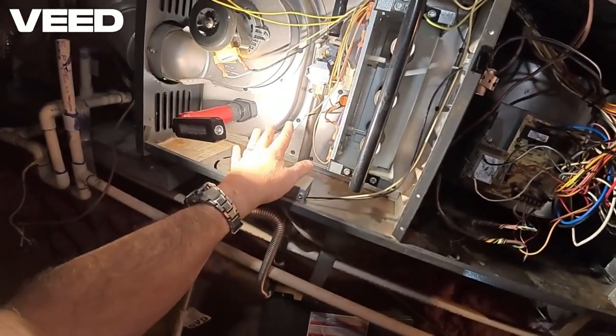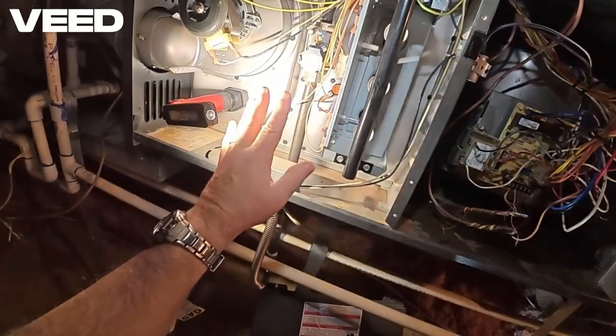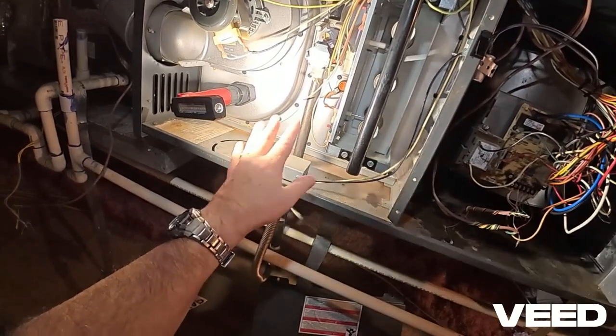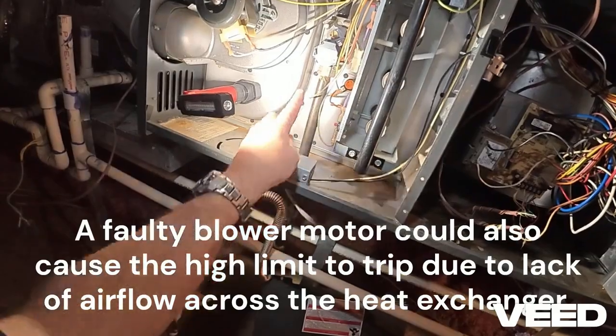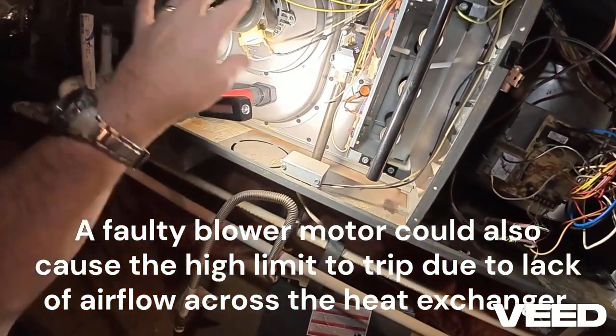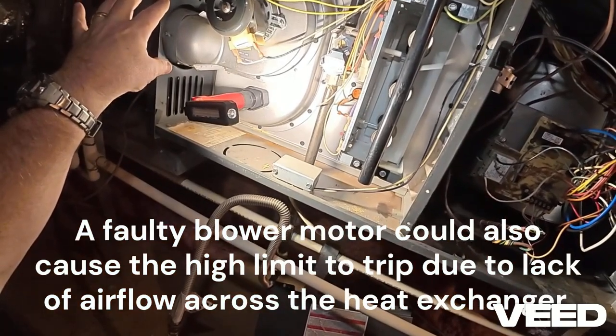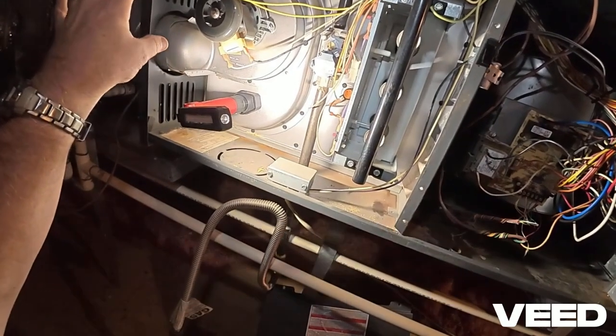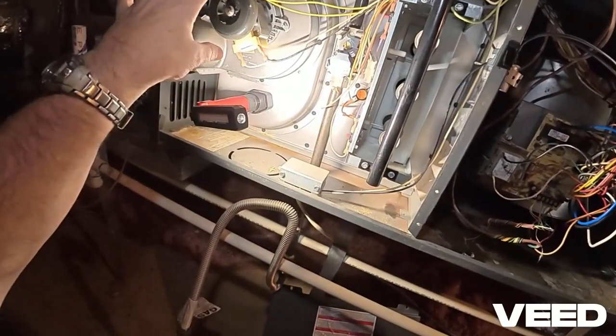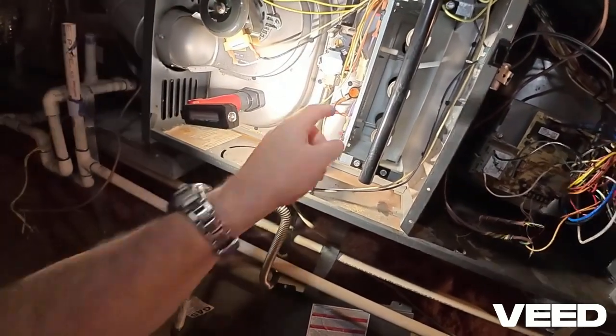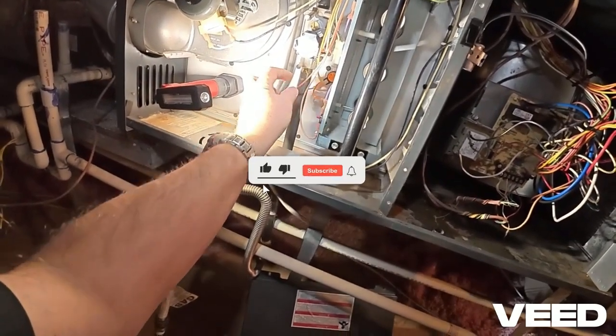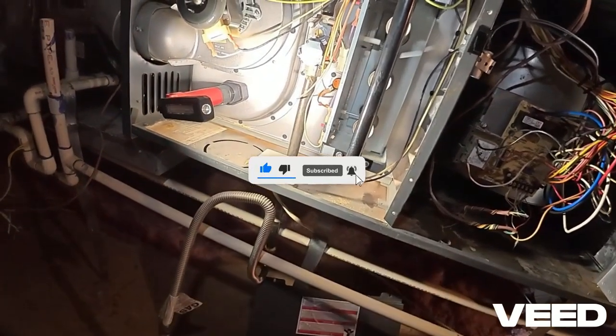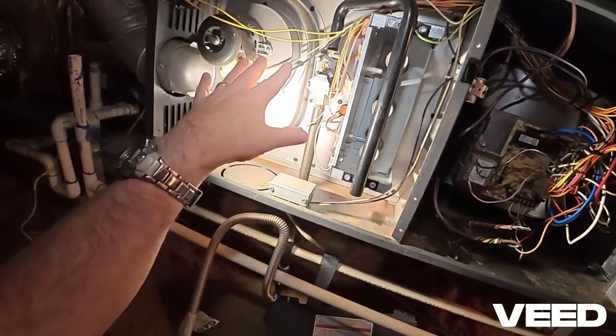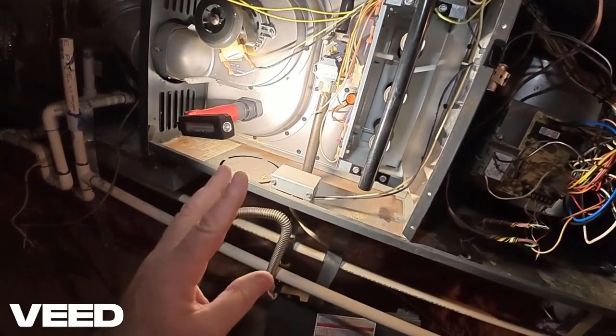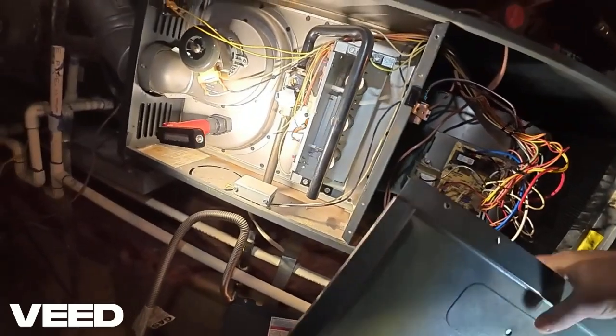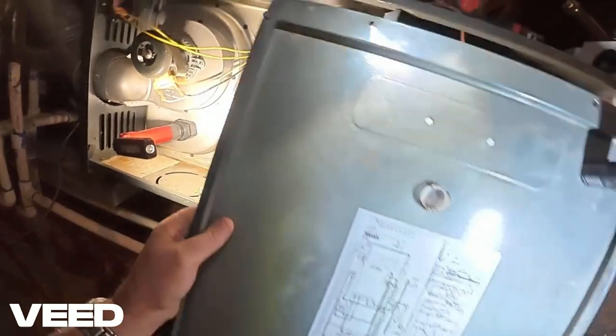So this is a safety. If you have a problem, say with a dirty filter or closed registers, and you have an airflow issue and it's not getting enough air across the heat exchanger to pick up and remove the heat, it will overheat, and this will open up and send a signal back to the control board of a fault and turn off the system. So that's the role of the open high limit. And again, it's often an airflow issue.